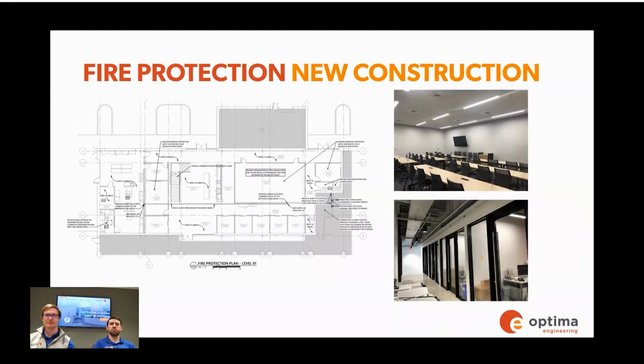So when we look at the new construction, you have to look at the architect's layout and adjust the fire protection system so that we still have the same coverage and everything is covered, even with new walls and new ceilings. So if there's a conference room with more people, or a wall that blocks where an existing sprinkler would have sprayed water, then we have to modify the system.